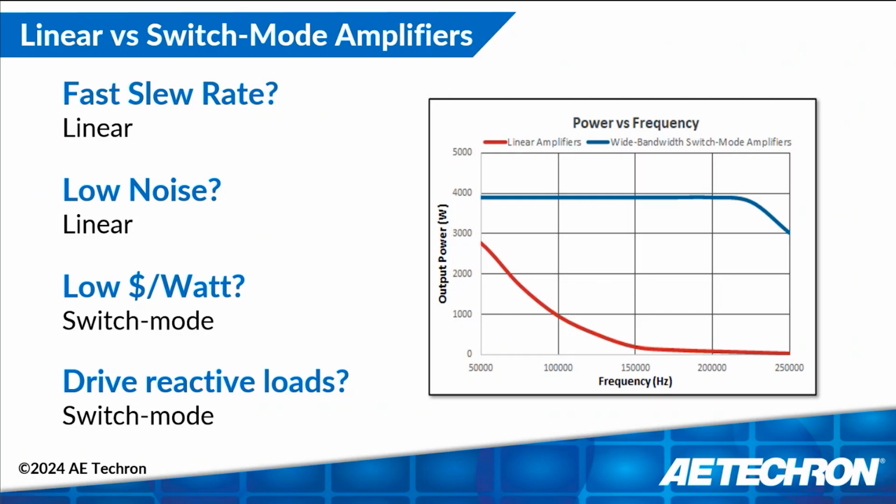So again, this is a unique application, but that's one that you actually see in test labs where they're driving reactive loads. Maybe they're doing capacitor testing, or like this, they're driving fans, or it could be a magnetic coil, a Helmholtz coil. All of those things are in test labs all over the world. So this is just an example of when reactive loads is maybe the biggest determining factor sometimes of what would make sense for a customer when it comes to switch mode technology.